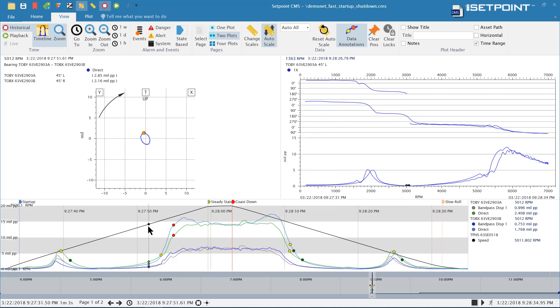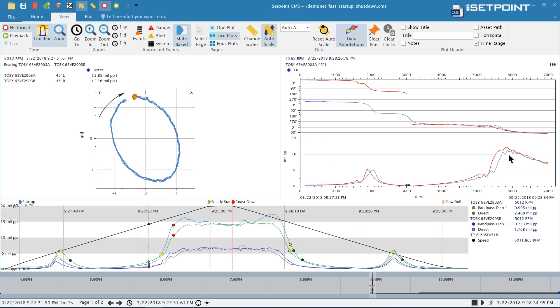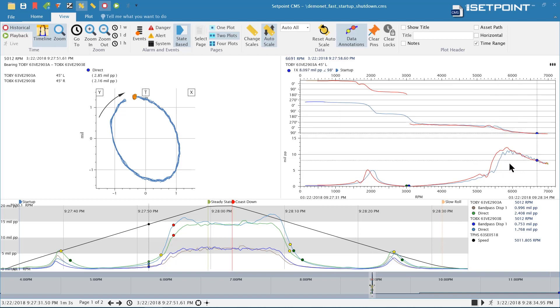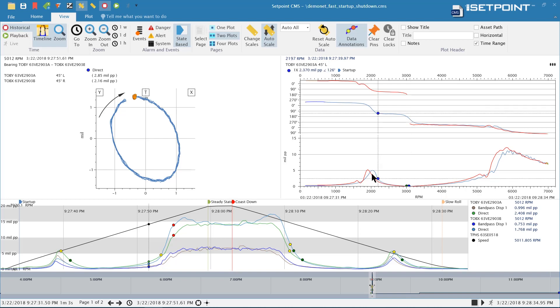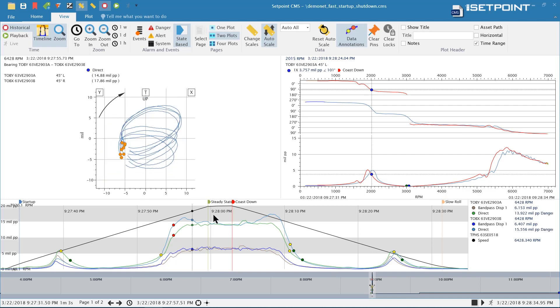Now that we have states, we can use those on our plots. To do that, from the view menu here we can turn on state-based displays. Now that colors the data based on what state it's in. We can see on the bode plot that you can easily differentiate the startup data from the coast down data, and you can see the steady state data here in the end. That makes it a lot easier to differentiate your data without clicking around on it to figure out what state it's in. As you click around on the data, the header will also show you what state the data at your cursor is in.